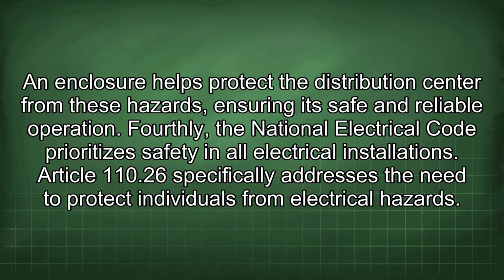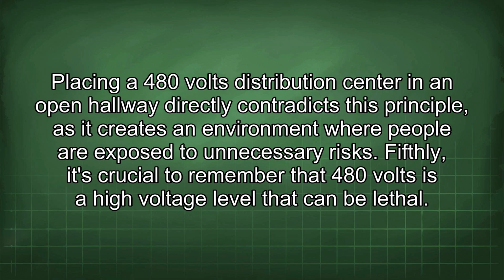Fourthly, the National Electrical Code prioritizes safety in all electrical installations. Article 110.26 specifically addresses the need to protect individuals from electrical hazards. Placing a 480 volts distribution center in an open hallway directly contradicts this principle, as it creates an environment where people are exposed to unnecessary risks.